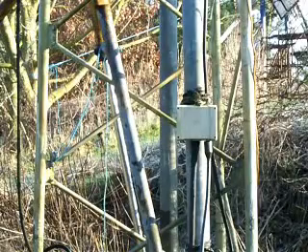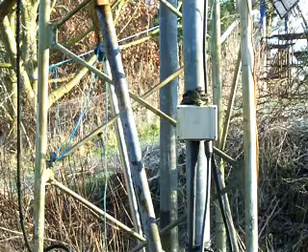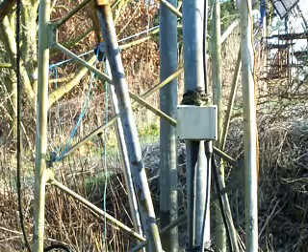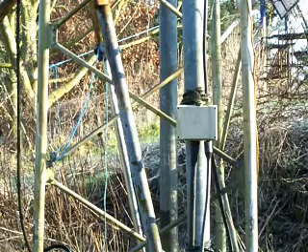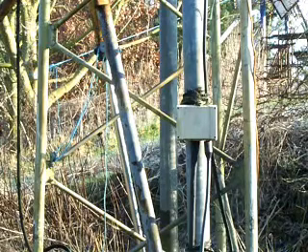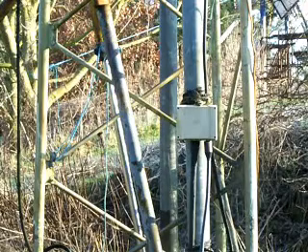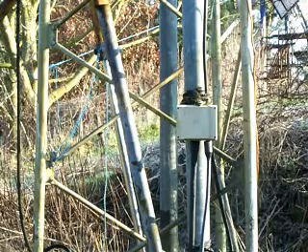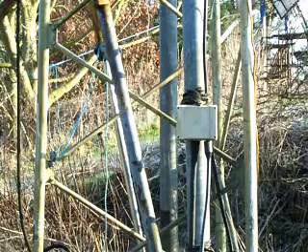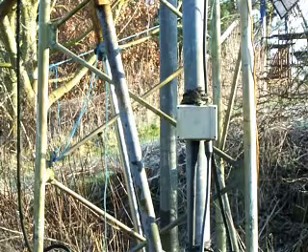Here we see the large armoured cables that bring the power from the turbine and off to either the grid tie or the battery shed. There are 3 cores in these cables, taking the 3-phase AC from the turbine. The cables need to be large enough to avoid volt drop. Volt drop is where the cables are not large enough to allow the current to pass freely, and so therefore power is lost in the cables.